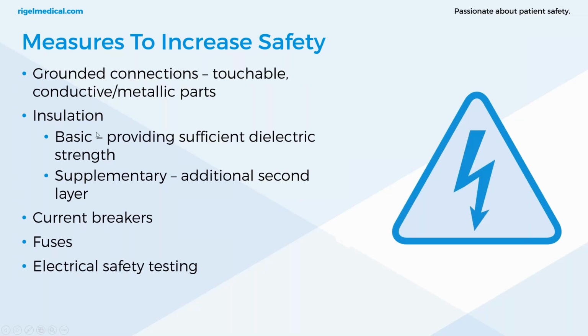There's insulation. This is another method of protecting users and patients. Basic is providing just sufficient dielectric strength, so we'll see this on class 1 devices. Supplementary, which will sometimes be referred to as class 2, uses supplementary protection and is provided by a double layer of insulation. So there's no earth connection required. You've already got that safety barrier by introducing an additional safety barrier.